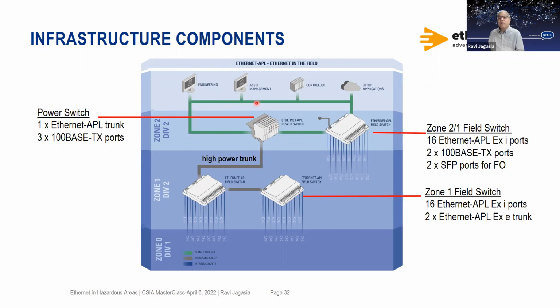The network on the back end is a regular commercially available Ethernet. Then you can power what you would label in the old days as high power trunk. You could power the field switches, the APL switches, and you could use them to connect to the field devices. These are the zone 1 solutions. These will be with 16 ports. Like if you remember 8 spurs, 12 spurs, field device couplers for the FF segments. Here we are having them as ports because we use Ethernet. So we have a 16 port solution here.